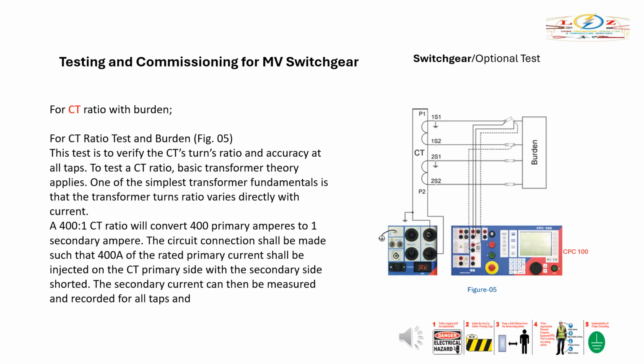The ratio test is required for CTs and VTs. For CT ratio test and burden, as shown in the arrangement drawing in Figure 5. This test is to verify the CT's turns ratio and accuracy at all taps. To test a CT ratio, basic transformer theory applies. One of the simplest transformer fundamentals is that the transformer turns ratio varies directly with current. A 400 to 1 CT ratio will convert 400 primary amperes to 1 secondary ampere. The circuit connection shall be made such that 400 amperes of the rated primary current shall be injected on the CT primary side with the secondary side shorted. The secondary current can then be measured and recorded for all taps.